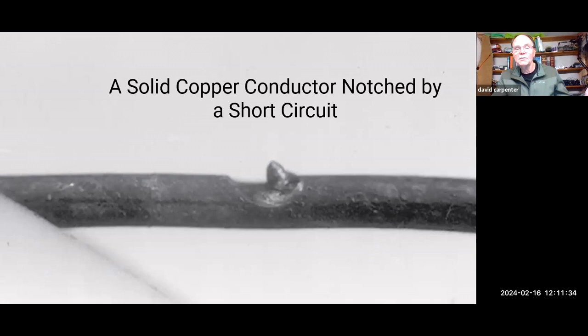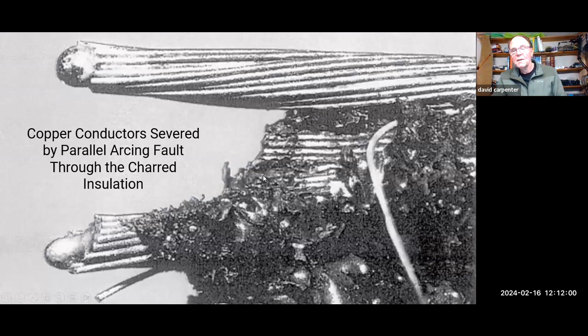This is one that's called a parallel fault, or a parallel arcing fault. So this is the wire, two wires, and the energy is actually arcing in between them, and all the insulation is destroyed. By the way, this picture is in NFPA 921, and 921 tells you how to look at that and determine what happens. That's the reason I want you to know about NFPA 921.